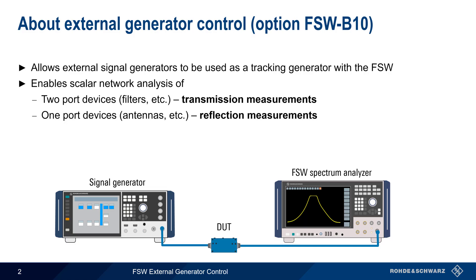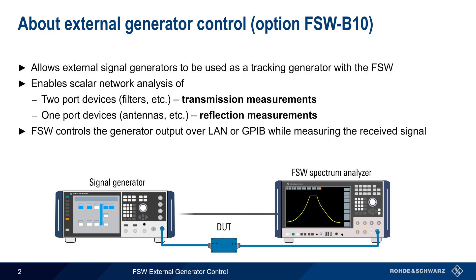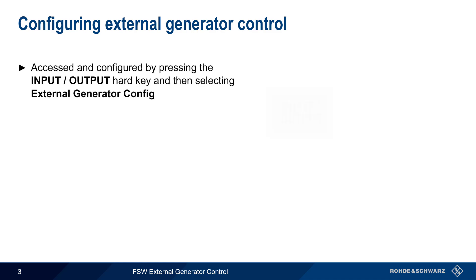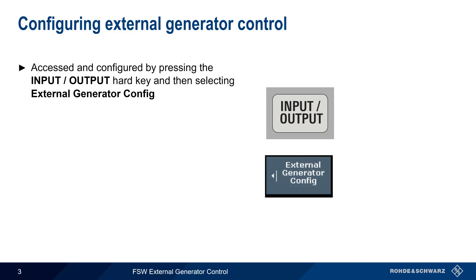For both measurement types, the FSW controls the output power and frequency of the signal generator over either a LAN or GPIB connection. External Generator Control is accessed by pressing the Input/Output hard key on the front of the FSW, and then selecting External Generator Config.